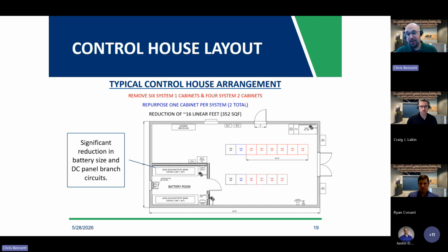And what does that look like from the top down inside the control house? Well, what we're talking about here with 2 dedicated racks for CPC, you would have your SCADA, HMI, and telecom racks on the left-hand side in the middle there. Your 2 blue racks now would be your CPC, and we would be eliminating all the racks in red. What that means physically is I can shrink the control house all the way from the right in by a significant margin. Less square footage means less HVAC. I know in Massachusetts recently there was a requirement for facilities above a certain size, so you might be able to dodge some of those.